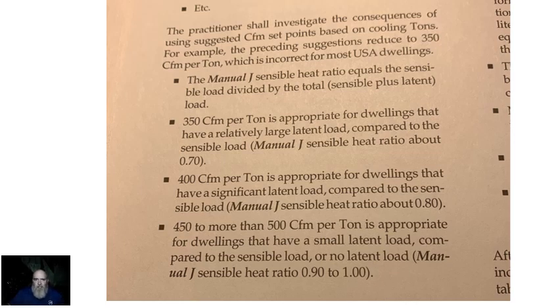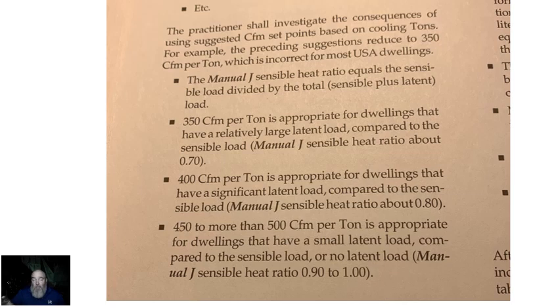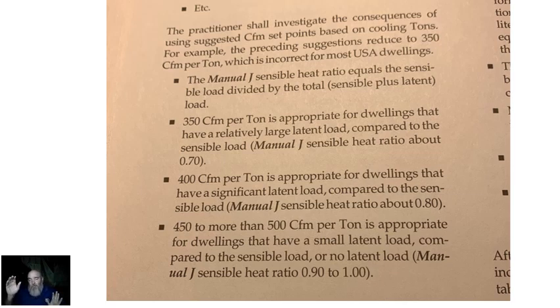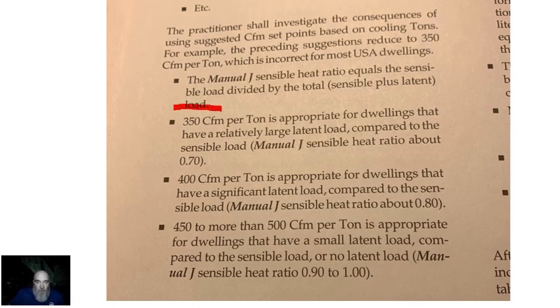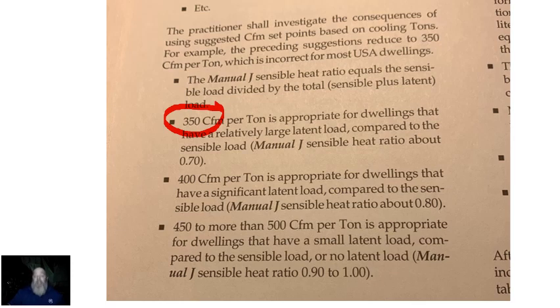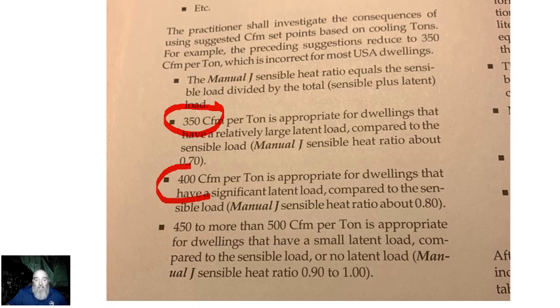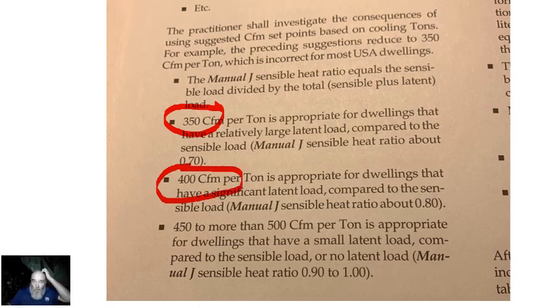This right here is just a heads up as to what your airflow should be. 400 CFM per ton is the equivalent of beer can cold. It's sizing a system and arbitrarily saying that you're using 350 a ton because you live in a humid climate. That's beer can cold. Doing everything based on 400 CFM per ton is beer can cold. They're rules of thumb.